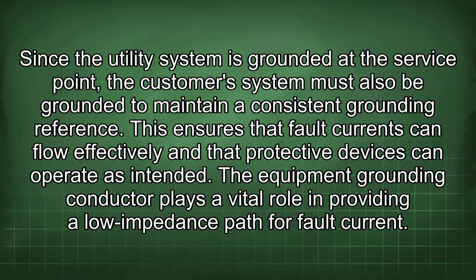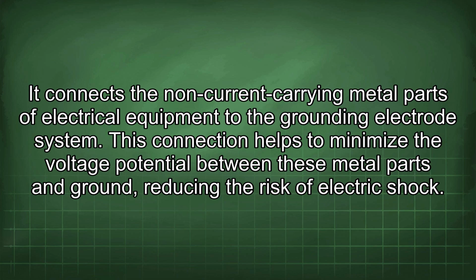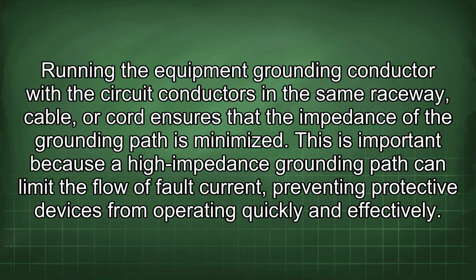The equipment grounding conductor plays a vital role in providing a low impedance path for fault current. It connects the non-current carrying metal parts of electrical equipment to the grounding electrode system. This connection helps to minimize the voltage potential between these metal parts and ground, reducing the risk of electric shock. Running the equipment grounding conductor with the circuit conductors in the same raceway, cable, or cord ensures that the impedance of the grounding path is minimized. This is important because a high impedance grounding path can limit the flow of fault current, preventing protective devices from operating quickly and effectively.